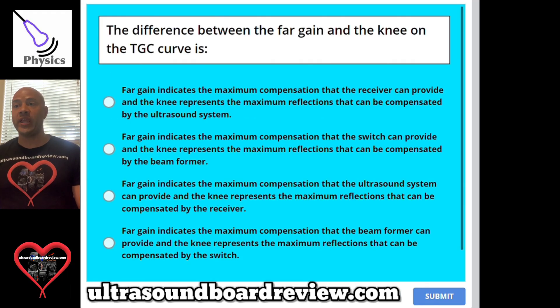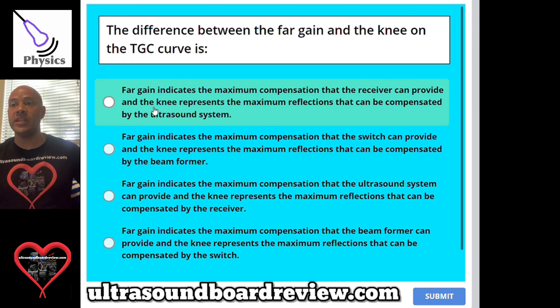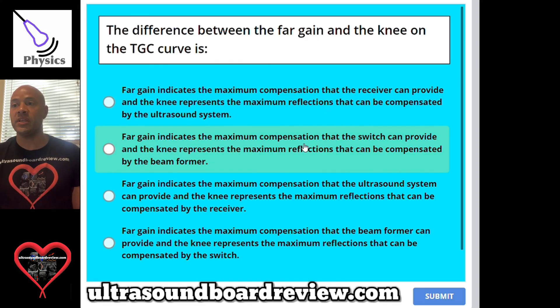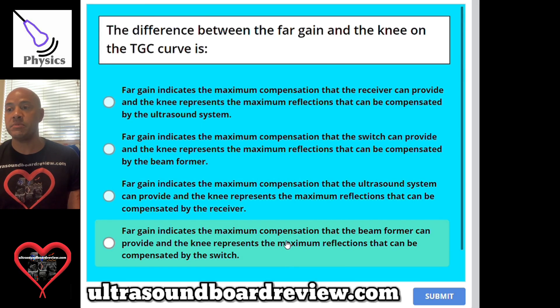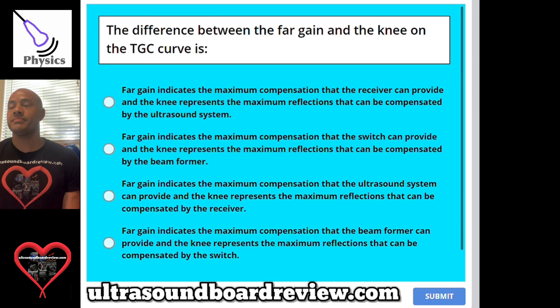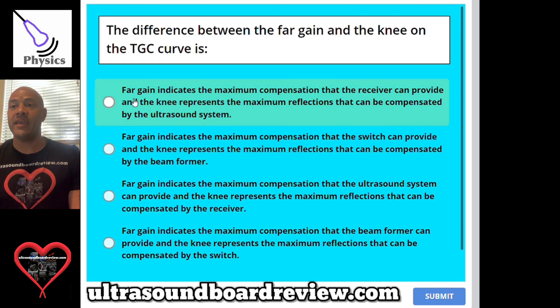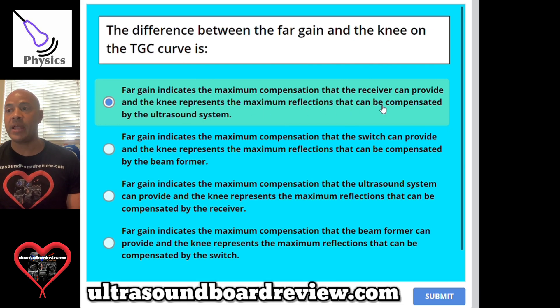Question 75: The difference between the far gain and the knee on the TGC curve — A, far gain indicates the maximum compensation that the receiver can provide, and the knee represents the maximum reflections that can be compensated by the ultrasound system; B, far gain is for the switch, knee for the beam former; C, far gain is for the ultrasound system, knee for the receiver; or D, far gain for the beam former, knee for the switch. The answer is A: far gain indicates the maximum compensation the receiver can provide, and the knee represents the maximum reflections compensated by the ultrasound system.